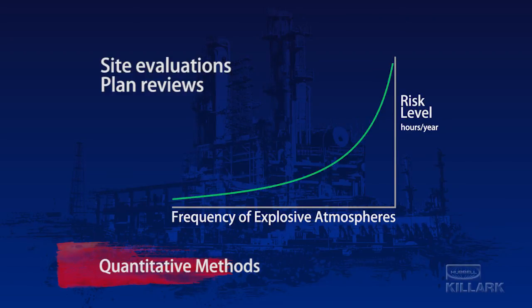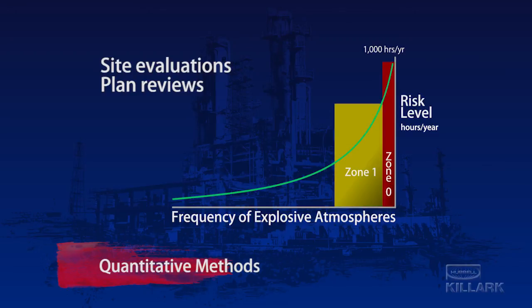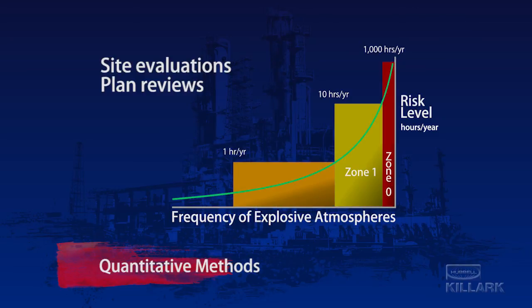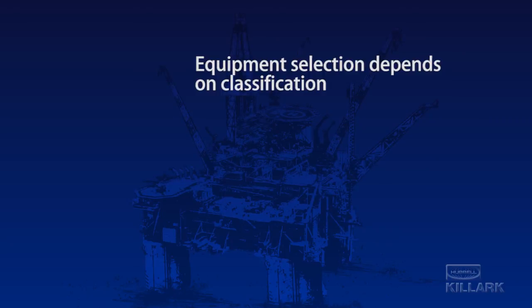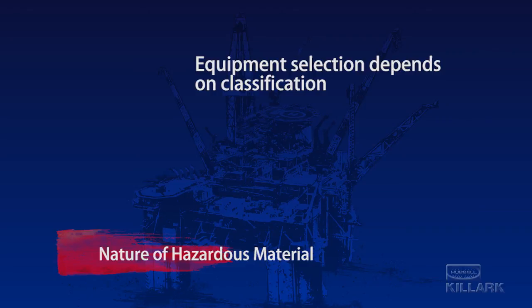When the occurrence of ignitable atmospheres exceeds 1,000 hours per year, the risk would be judged to be Zone 0. Locations that were considered to be Zone 1 could experience explosive atmospheres between 10 hours per year and 1,000 hours per year. And under this method, when the issues occur less than 10 hours per year, the designation would be Zone 2. Of course, these parameters must be adapted to local practices, experience, and circumstances. Since it has a very important impact on the equipment that will be selected for the application, the risk analysis or classification of the hazardous location must also include information about the nature of the hazardous material that could be present in the atmosphere.